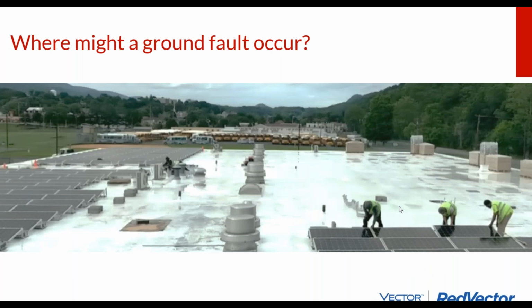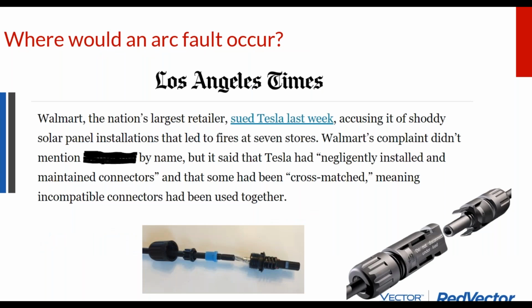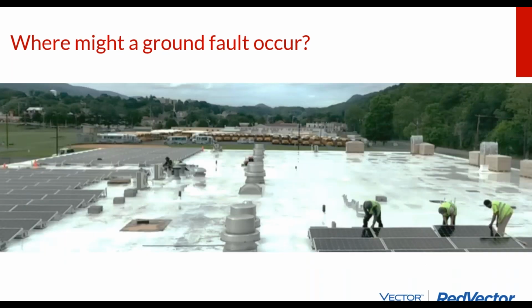They can also occur to describe a fault between two powered phases. So if you have two powered phases that are of different voltages, whether it's a 48 volt circuit and a 12 volt circuit, or a 120 volt circuit and the oppositely phased 120 volt circuit, arc fault can occur between those two as well. A ground fault occurs between a powered conductor that's faulting into ground. And so an arc fault could get a lot more dangerous if it becomes a ground fault.